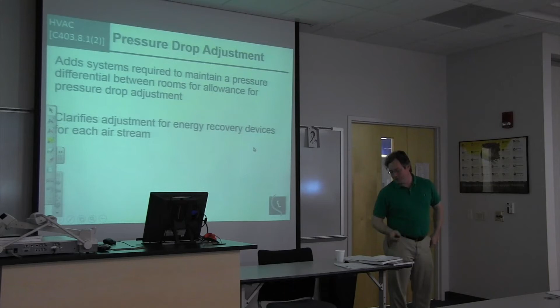So you might run into some of these. Pressure drop, this was more of a clarification in the table as far as your pressure drop allowance. Something else that needs to be on the prints is fan horsepower rating. Motor ratings for your fans need to be on the prints listed. However, those smaller than 1 horsepower don't have to be on there, so your fractional horsepowers don't have to be listed.